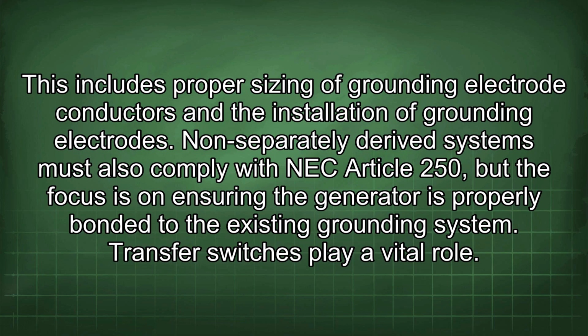This includes proper sizing of grounding electrode conductors and the installation of grounding electrodes. Non-separately derived systems must also comply with NEC Article 250, but the focus is on ensuring the generator is properly bonded to the existing grounding system.